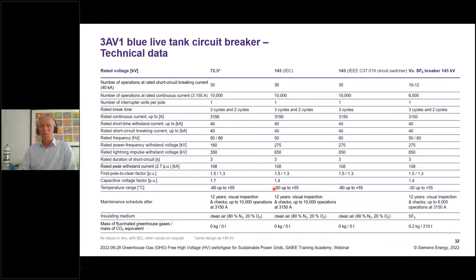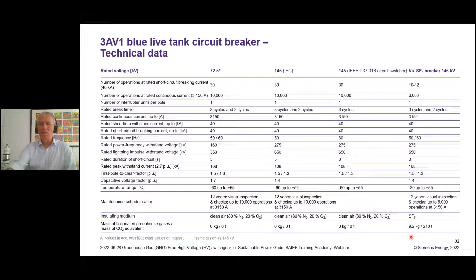Most of the other data are identical as far as the current and the short circuit are concerned. Going to the lower side, you see that it has a better performance at lower temperature, so it doesn't need any heating or mixed gases like other SF6 technologies, because SF6 usually liquefies at -25. You also see, especially in the maintenance schedules, that there is less maintenance related to the new technology than to the old. The checks don't have to be after 6,000 operations, but after 10,000 operations. What's most important, and was the initial point, is that there is 0 fluorinated greenhouse gas and 0 CO2 equivalent connected, compared to SF6 technology. This is the value of one breaker.